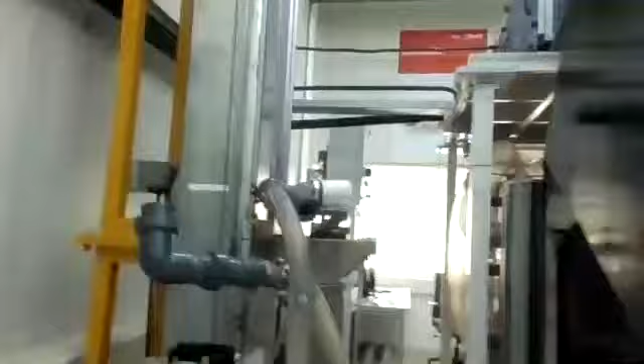This is the priming tester, you can see it here. It looks like a crane. You can connect the pump here, and we have a control to lift the pump from 0 meters, that is the lower ground level, up to around 30 meters. You can move the pump up and down and perform the testing. This is normally for testing the priming setup, to check whether the pump is able to prime or not.